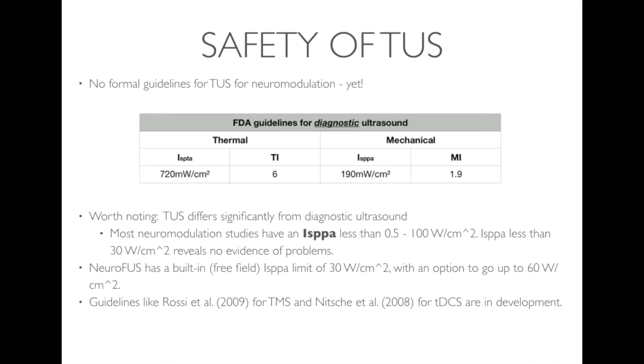You can refer to the safety papers if you want to know more, but most neuromodulation studies have an ISPPA between 0.5 and 100 watts per centimeter squared, and don't really reveal any problems. And if ISPPA is less than 30 watts per centimeter squared, it hasn't revealed any problems at all.